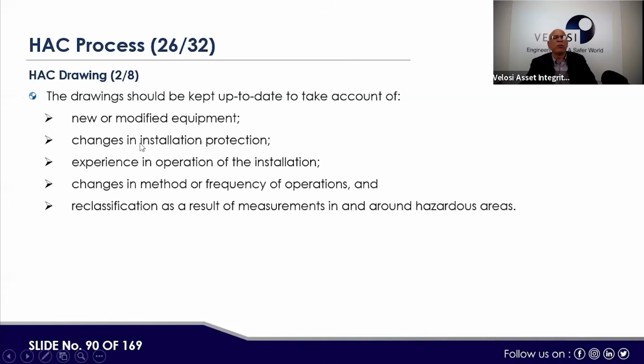New or modified equipment, changes in the installation which need protection, experience in operation of the installation, change in the method or frequency of operations, and reclassification as a result of measurements around the hazardous area. So if we have an as-built hazardous layout drawing, we can make the HAC drawing very easily.